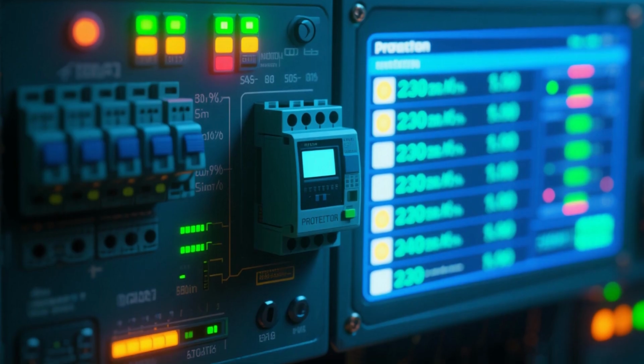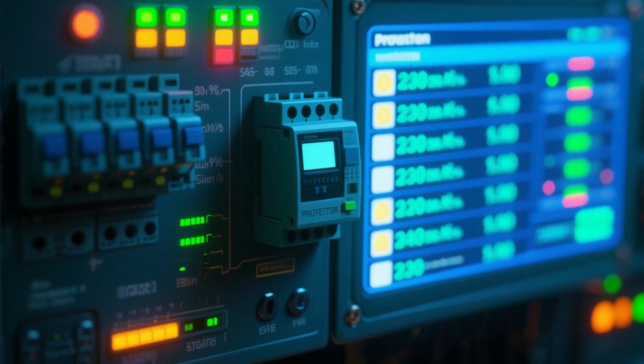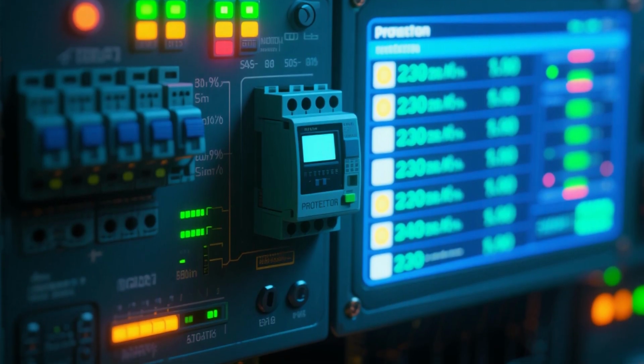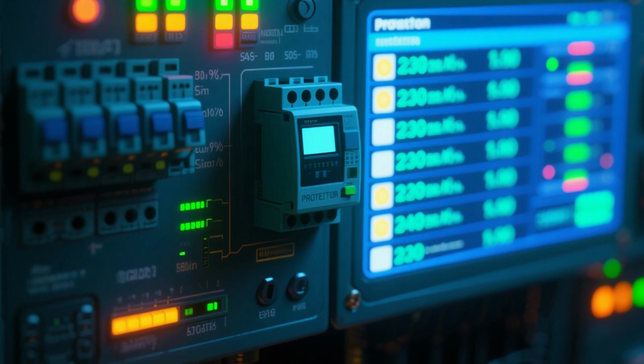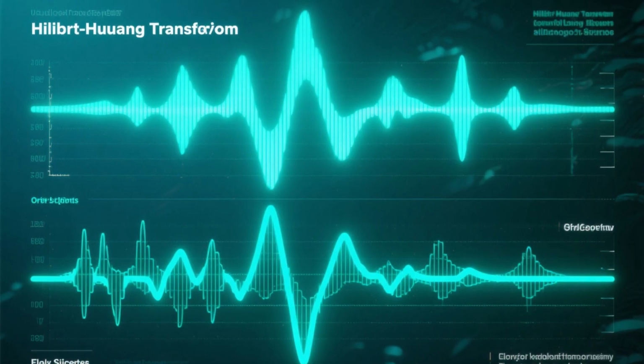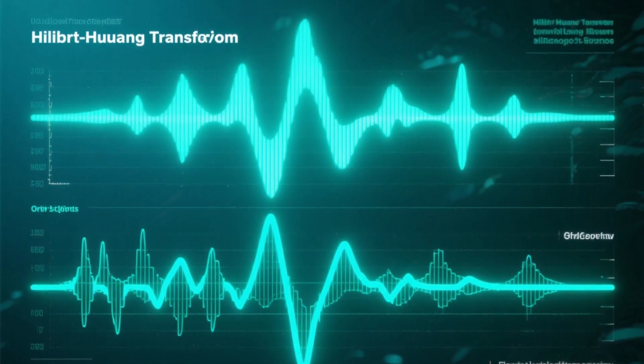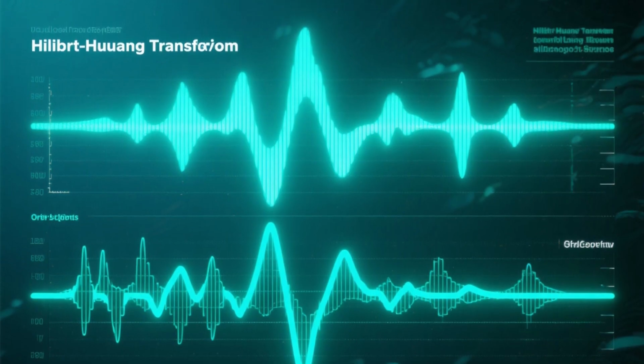By monitoring these coefficients, a protection relay can detect a fault with incredible precision and speed. The Hilbert-Huang transform, or HHT, is another sophisticated technique, particularly well suited for analyzing nonlinear and non-stationary signals, which are common during power system faults.